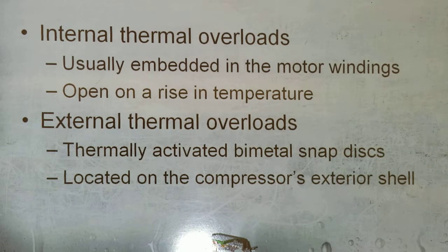What does inherent mean? Internal. Okay. What does it say? Inherent motor protection. Internal thermal overloads, usually embedded in the motor winding. They open on the rise in temperature.